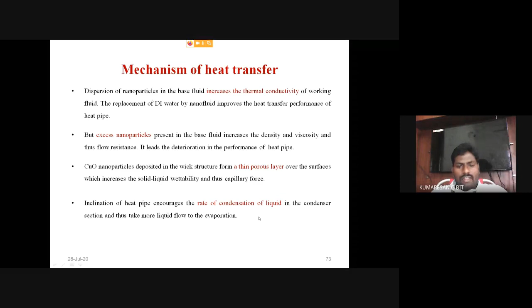Then a larger tilt angle. Okay, even if you are tilting that sintered wick heat pipe beyond 45 degrees inclination, closer to the vertical position, it results in the deterioration of performance. It is due to the faster condensate return, which affects the function of the evaporator section.